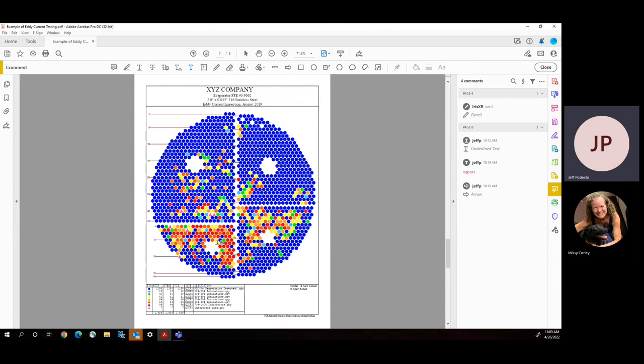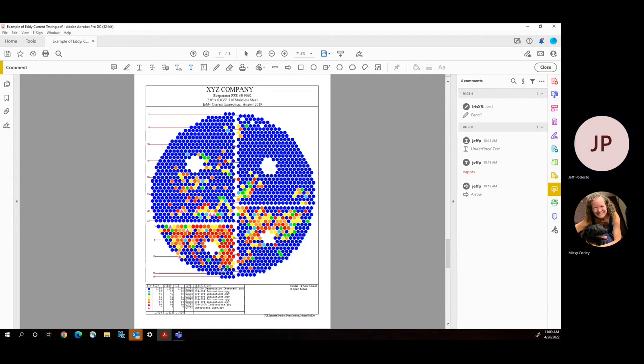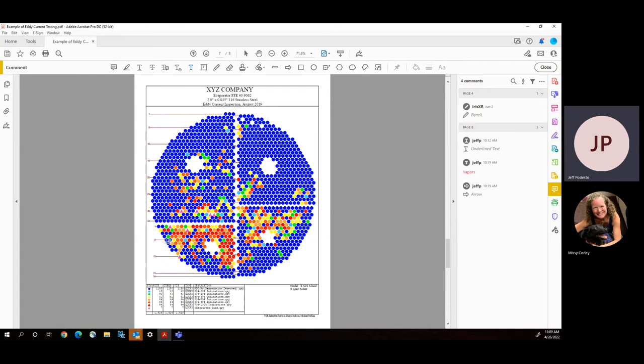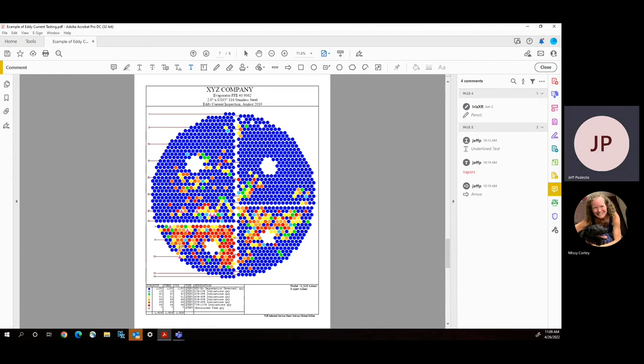And so, the feedback tells us we've got a corrosion problem, it's in the highest concentrations, and in this case, the customer basically just took this fourth pass and shut it off and quit using it. That was a reasonable recommendation and option, and it allowed them to continue operating and making decisions on what they're going to do with this last quadrant. Could be retube, or they could decide to replace the whole calandria. Those are some of their options that they're looking at right now. But they do have a short-term solution, which is just not to use this section and block it off.